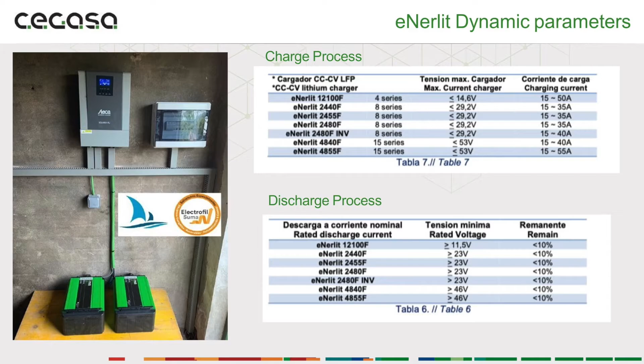So as such, they are treated as an unmanaged battery. It's important to say - we'll repeat it later - that whenever we are connecting the settings in the inverter, we choose the option of lead acid. We don't go for lithium because inverters might have a special lithium option with other requirements, but since we're using them without communications at all, we set the inverter as lead acid and then introduce the values corresponding to the battery itself.